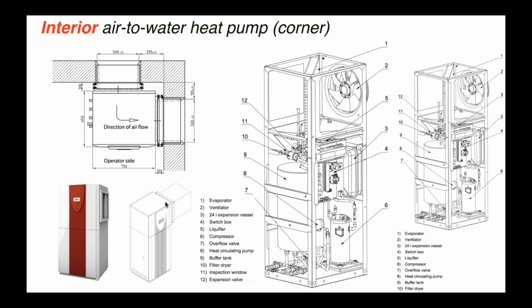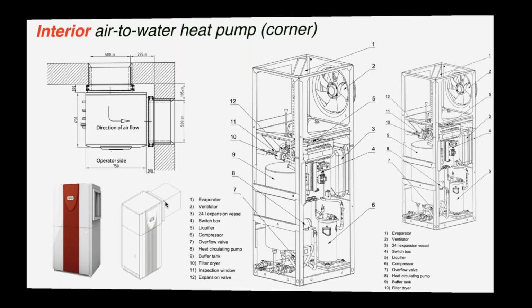So I really would encourage this kind of a heat pump to be available in the U.S. It's not going to work everywhere. It would work nice in slab on grade buildings where your exterior walls are all above grade. Your mechanical rooms are typically above grade. If it's below grade, that presents a difficulty in terms of trying to get that outside air. You'd have to go up and out. So again, it's something I want to show you just as a concept of how the generic model of an air-to-water heat pump can be applied.